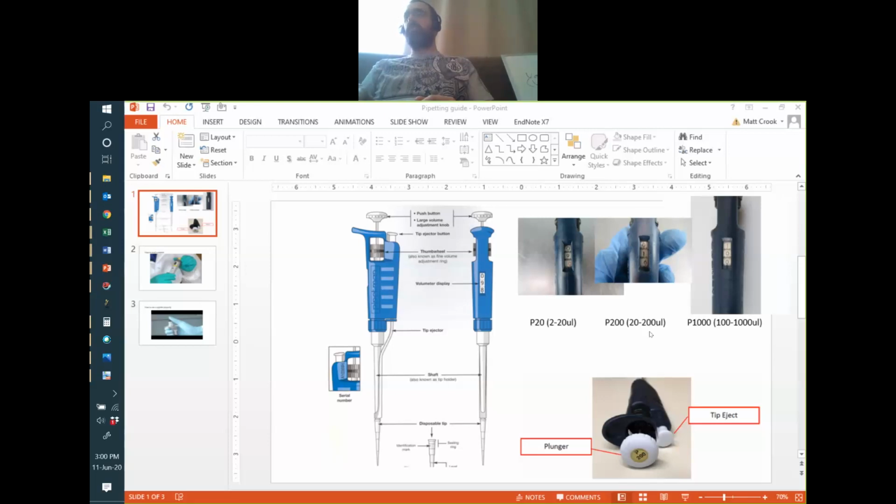So we've got a P200. The top one would be hundreds, again the largest digit, then tens, and singles. So this would be 016, which would be 16 microliters, and that's actually below its proper range. Whatever lab researcher is doing that needs a slap on the hand. And then the same again for the P1000: thousands, hundreds, and tens. So this is reading 1,000 microliters, or 1 milliliter.